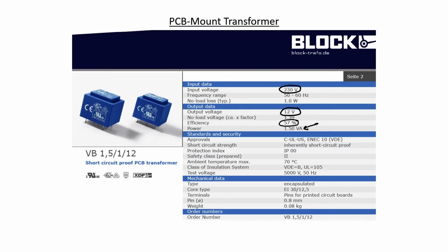And in order to express that without any confusion, that transferring of power typically has units of volt amps rather than watts. That's why here on the data sheet, the no load loss is typically 1 watt. The unit here being watt because the loss is inside the transformer itself. We can see that the frequency range for this particular transformer is at our line frequency. The purpose of this transformer then is to design power supplies. It transfers the 230 volts that one might find as line voltage into 12 volts here on the secondary side.